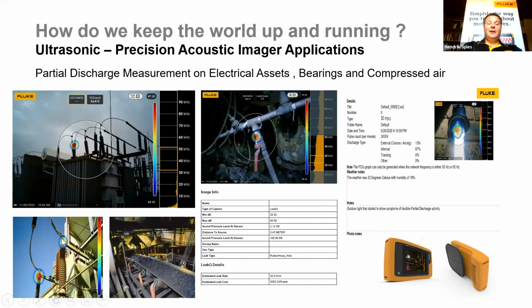And then, as I said, any other electrical asset, medium, high, low voltage, will be able to pick up partial discharge activity. The big thing for most industrial customers is compressed air. Typically this is an example where we've got a compressed air leak, which we detected just on the threaded connection of this tap. And now we've measured the distance and the severity according to our artificial intelligence scale. And now we can tell the customer, which is you, what is the estimated leak rate and what is the actual cost of energy wasted because of this air leak.